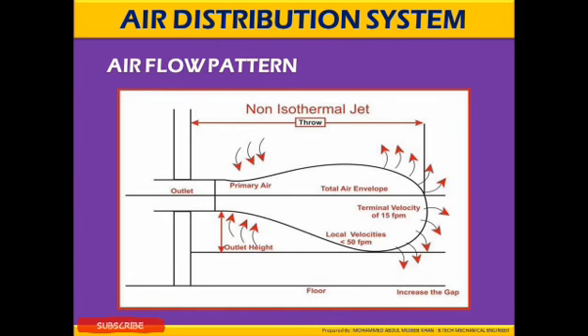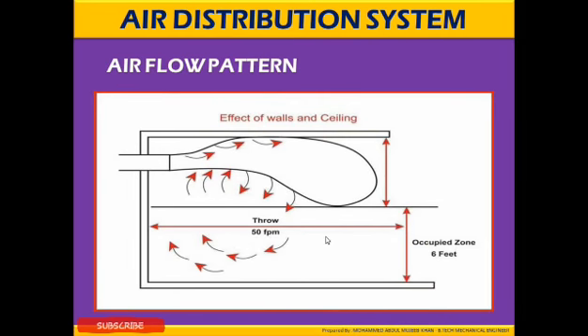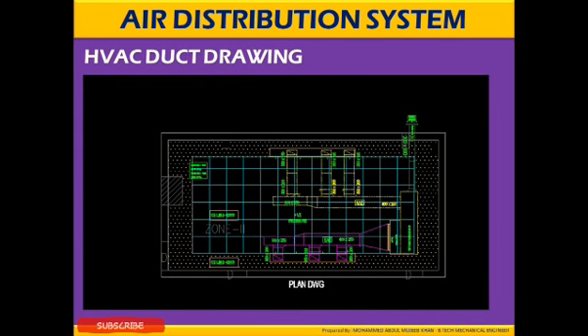Here is the plan view of an airflow pattern. As you can see from the outlet, the primary air comes out and it is distributed into the room and the floor. Here is the sectional view of an air duct, and the airflow affects the walls and the ceiling and the throw from the duct to the room. HVAC duct drawing. This is one of the simple examples of a HVAC duct drawing which is connected to the fan coil unit, the supply air duct and the return air duct.